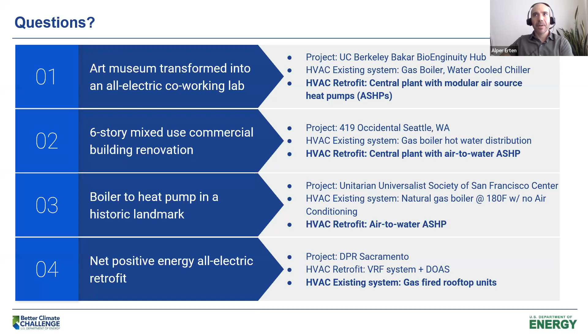I'll start with Alper. Concerns about peak loads for any of these locations? You mean like having an electric system. For the cooling side, we don't have any concerns. The air source heat pumps operate very similar to air-cooled chillers. They can provide really low temperature chilled water, down to 44 degrees, no problem there.